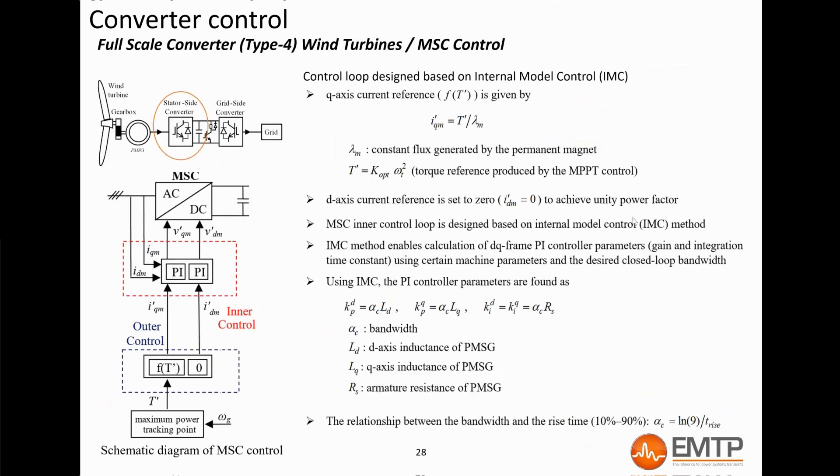On the machine side, the DQ-transformation angle follows the permanent magnet machine flux. The Q-component corresponds to the real power, and the D-component to the reactive power. Therefore, by controlling the Q-axis current, the converter controls the machine electromagnetic torque. The D-axis current is controlled to zero, as there is no need for reactive power on the machine side.